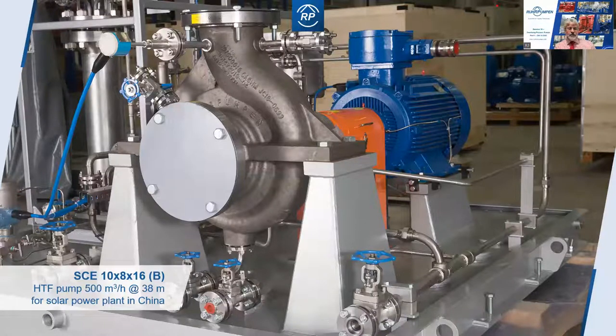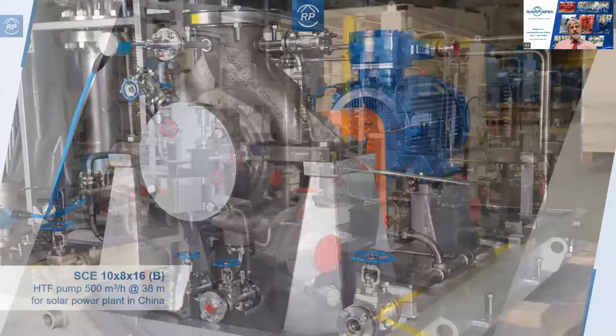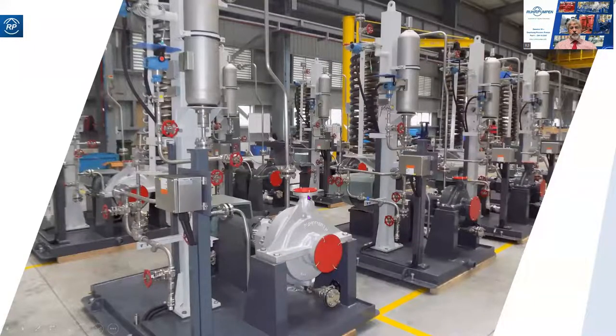A couple of slides to illustrate how different an API pump is than an ANSI pump. This first one is a large pump with 10x8-inch nozzles. Notice the centerline support and the skid-mounted auxiliary process piping. And even at the smaller sizes, this is an API pump with 2x4 nozzles. You see the base plate extended to take all this auxiliary piping, this plan 53 seal piping. This is very different from the ANSI pump that we saw earlier.